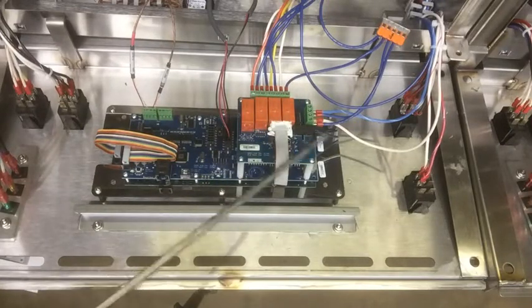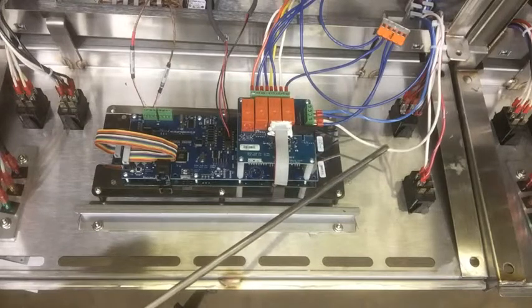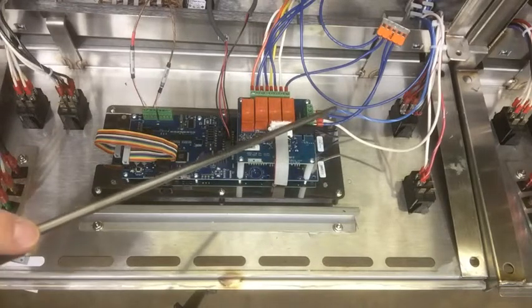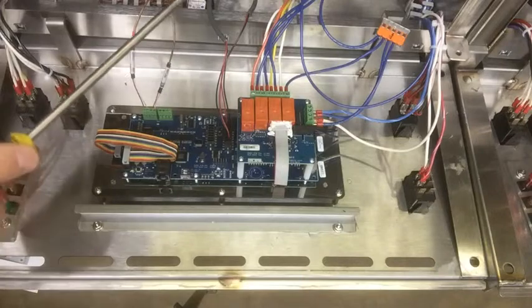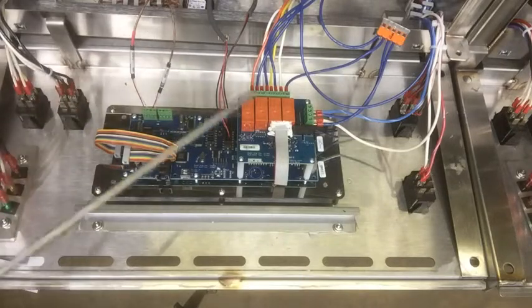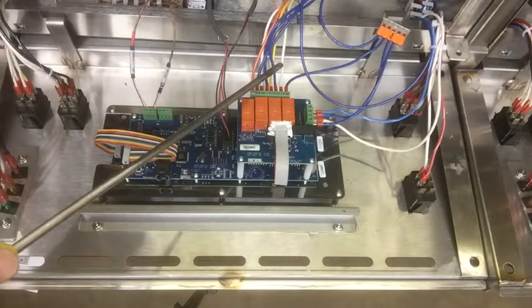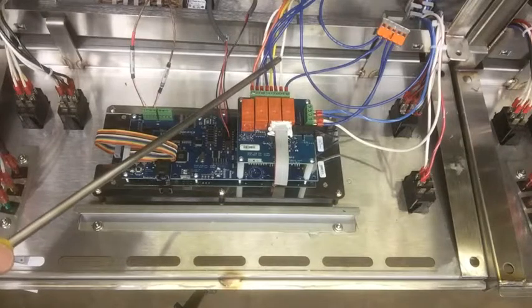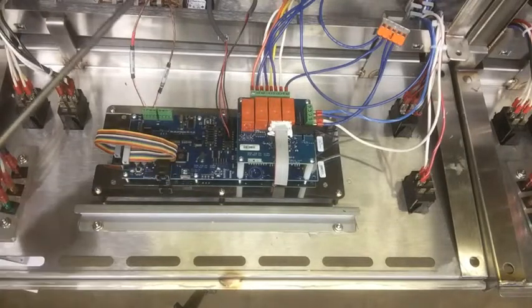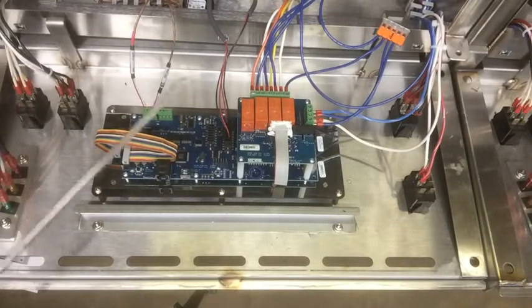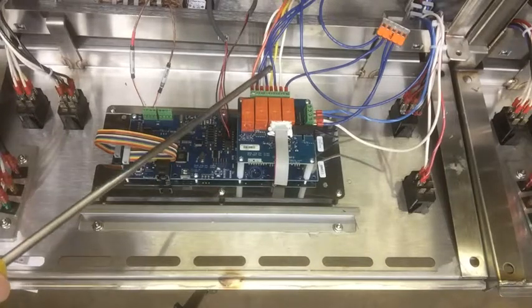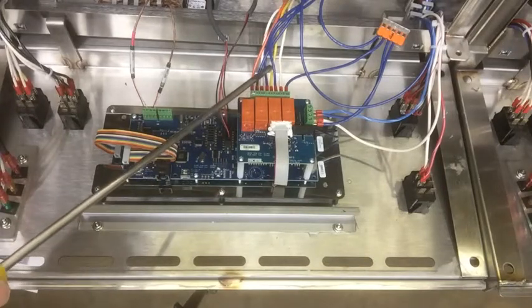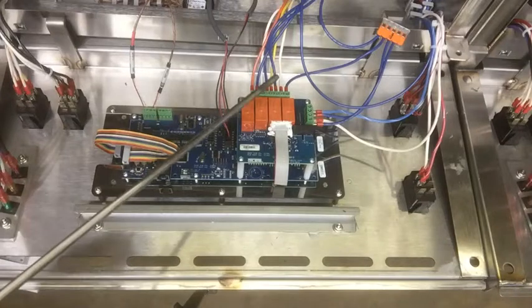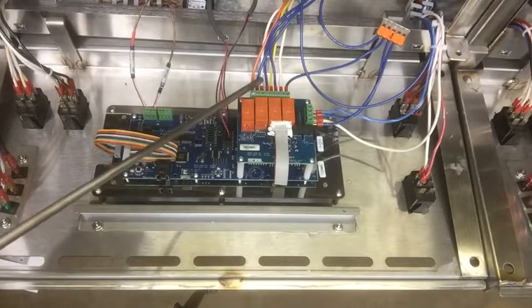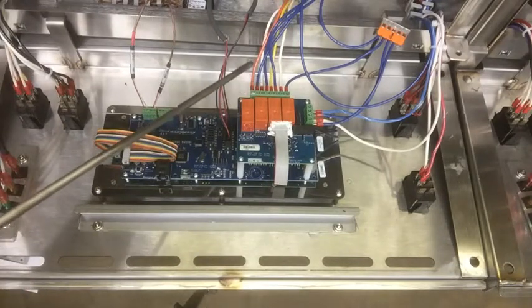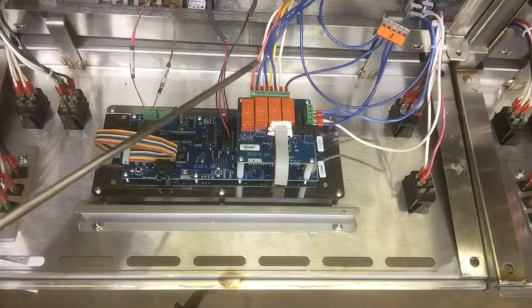On the outputs, we've got our alarm output on the white wire. The blue with the white is going to the heat contactor and pulling that in. This white with a yellow stripe is the down for our right-hand elevator. The solid yellow is the up for our right-hand elevator. Our left elevator is the white with the orange for down, and solid orange for the up.